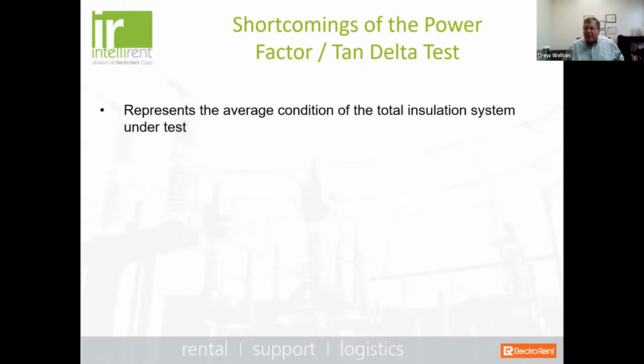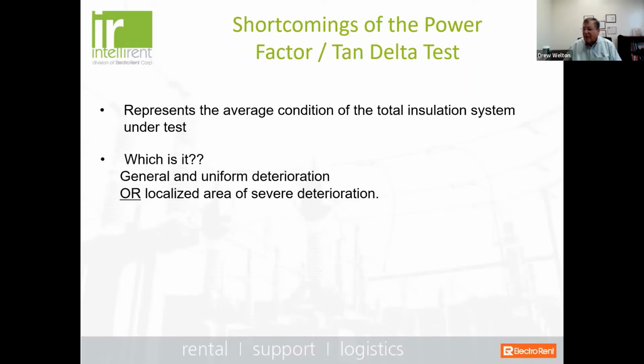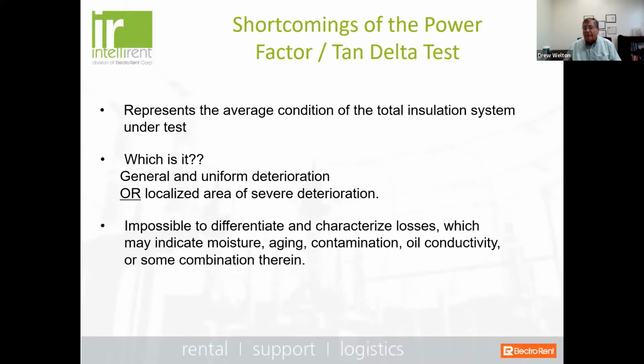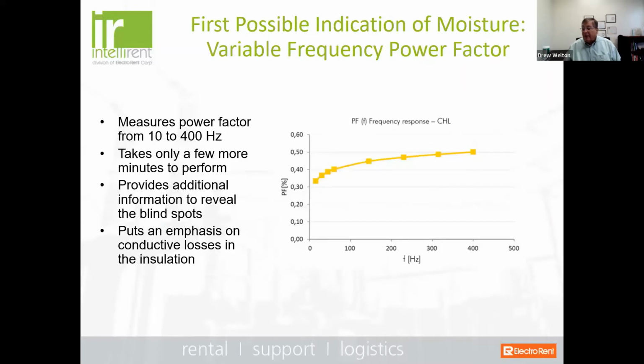So what are the shortcomings? Well, it represents the average condition of the total insulation system under test. You don't know if it's going to be a general and uniform deterioration, or if it's a severe localized area of deterioration. We just don't know. Now, in terms of moisture, your CHL measurements can show a slight elevation at 60 hertz. But the problem is it's impossible to differentiate and characterize losses, which may indicate moisture, could be aging, contamination, oil conductivity, or some combination thereof.